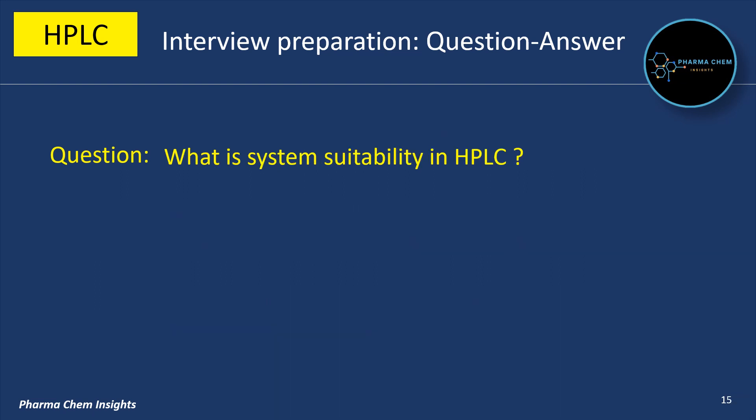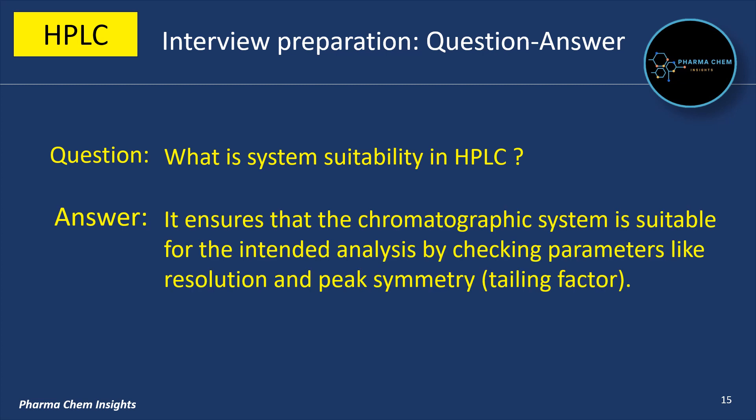What is system suitability in HPLC? System suitability ensures that the chromatographic system is suitable for the intended analysis by checking parameters like resolution and peak symmetry, i.e., tailing factor.